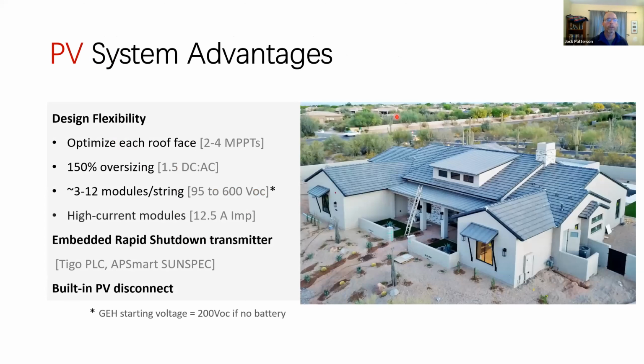On the PV side, what are the advantages, not just to our PV inverter, but to our hybrid inverter? Because our hybrid inverter doesn't lose the PV advantages. Often with some other brands, if you take their PV inverter compared to their hybrid, or just look at their hybrid, it doesn't have the full spectrum of PV specs you'd like to see. Ours are the same for the PV and the hybrid. So starting with the number of MPPTs, or maximum power point trackers, that is the number of strings you can optimize.